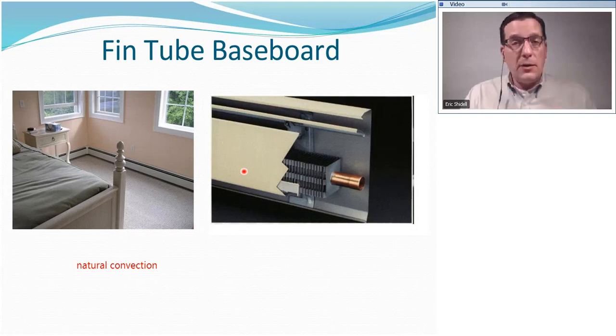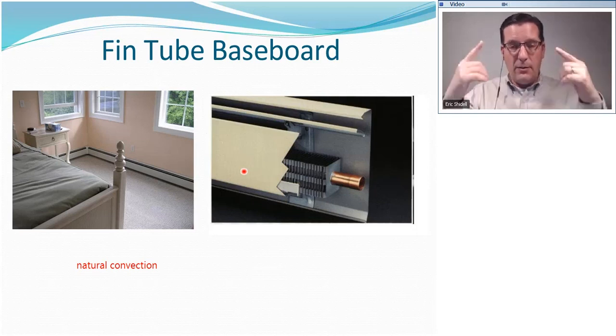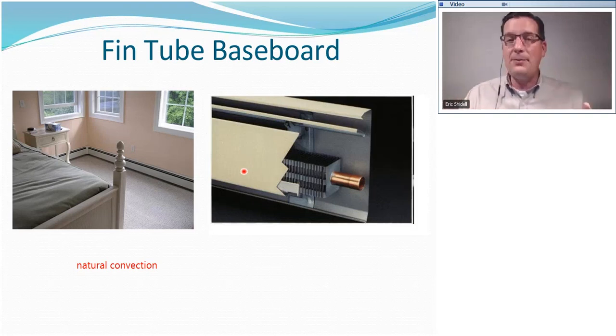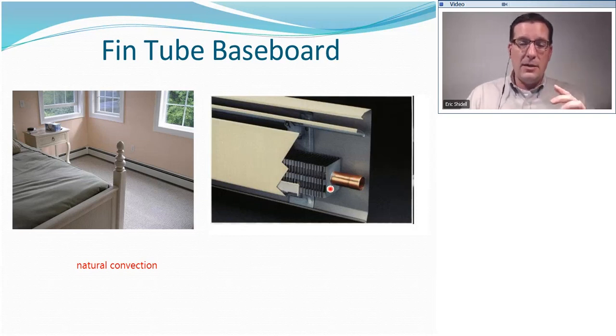Another thing I want you to be aware of with the fin tube baseboards is noise. Remember, one of the advantages of hydronic heating is they're supposed to be silent. Well, as they get older, these aluminum fins that are literally clamped, they're not soldered, but just clamped onto the copper tube, over time, through expansion and contraction, will loosen. They won't be clamped on as firmly as they were. If you're of a mind to, you can sometimes grab hold of these fins and literally twist them on the pipe. And this is an indicator that they're getting loose.